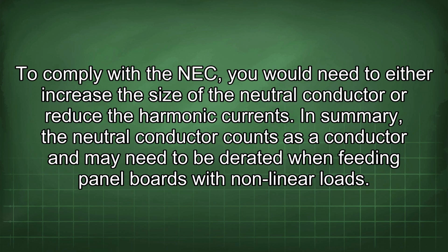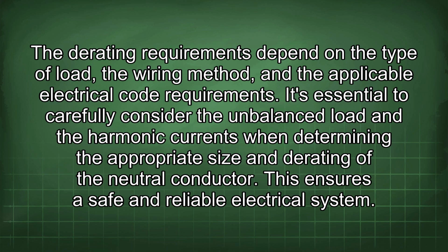boards with nonlinear loads. The derating requirements depend on the type of load, the wiring method, and the applicable electrical code requirements. It's essential to carefully consider the unbalanced load and the harmonic currents when determining the appropriate size and derating of the neutral conductor. This ensures a safe and reliable electrical system.